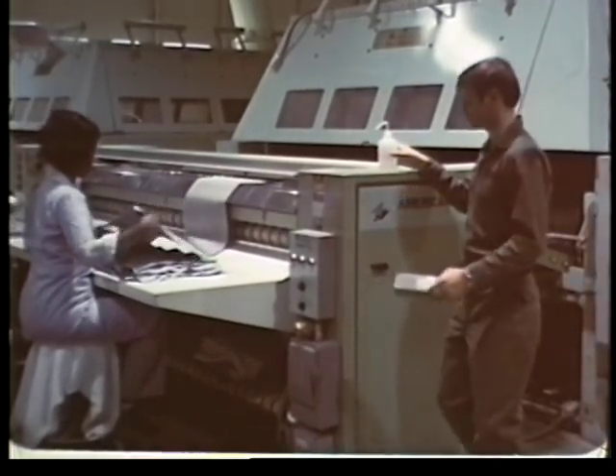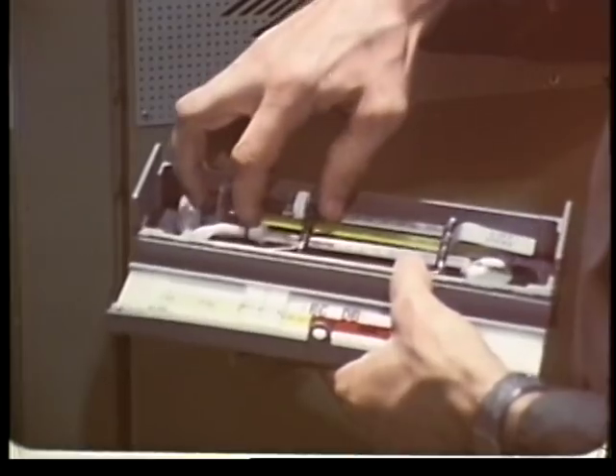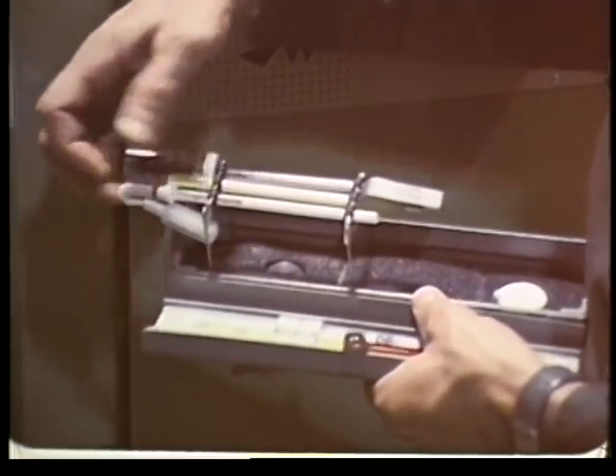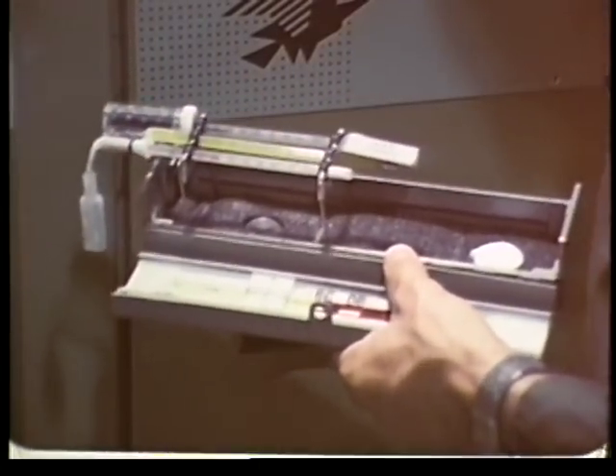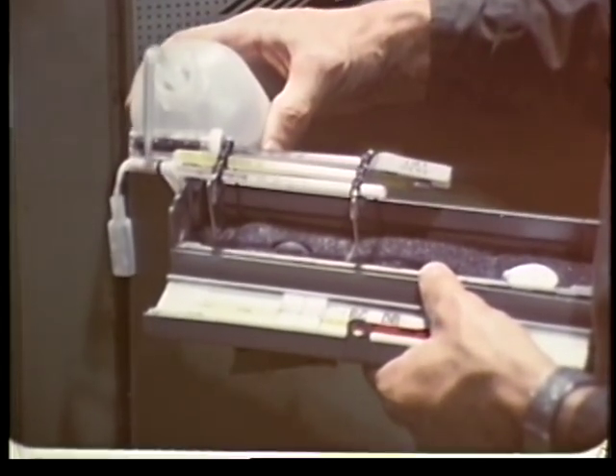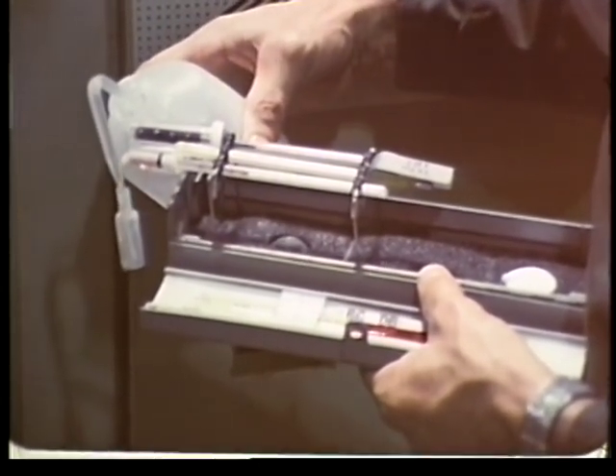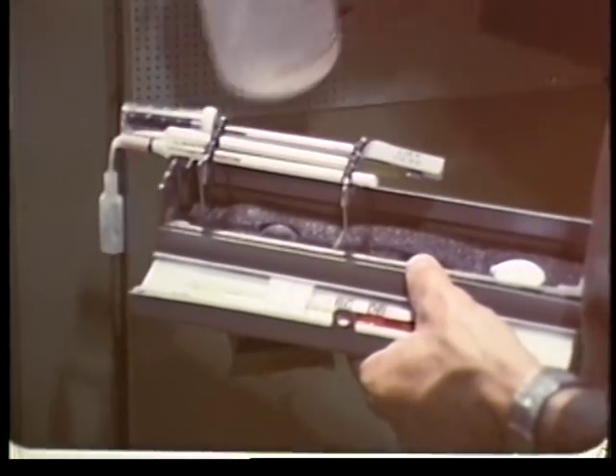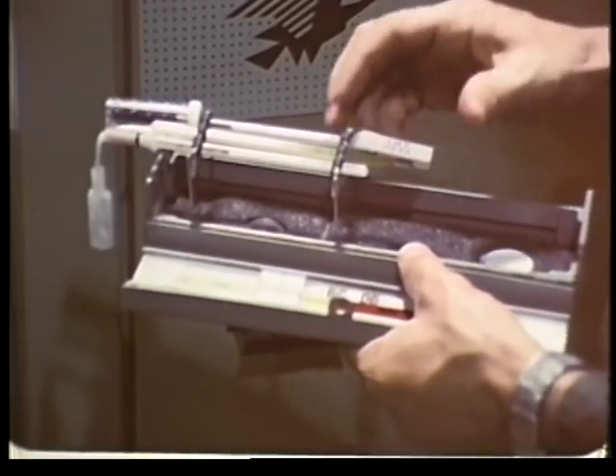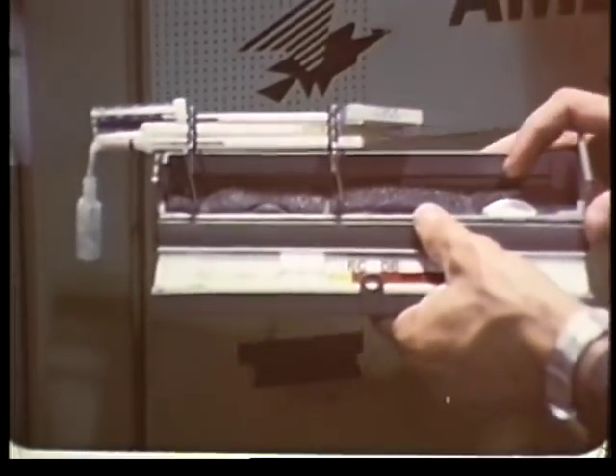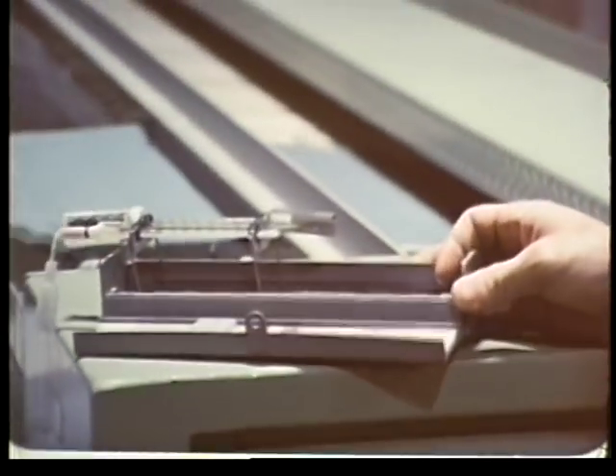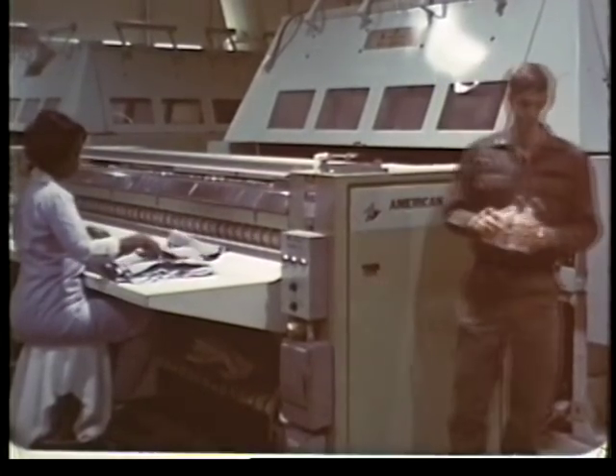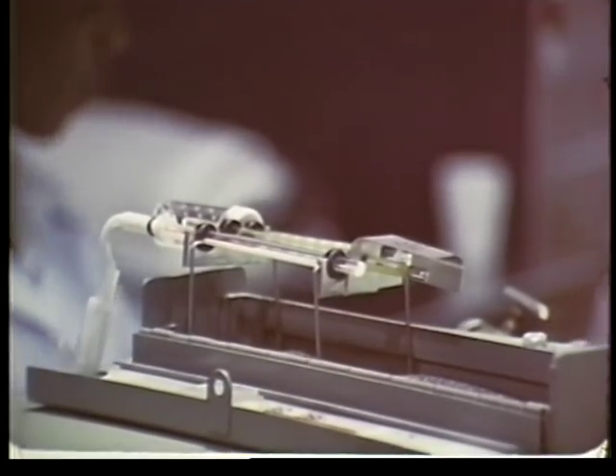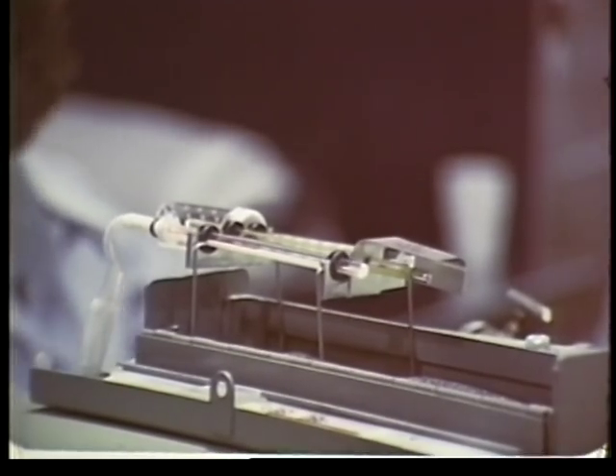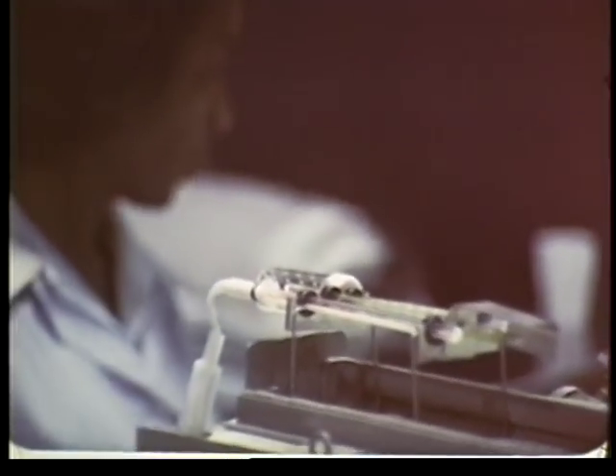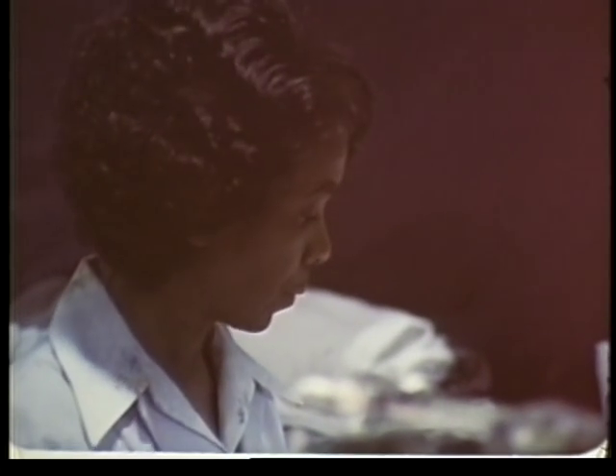You begin the evaluation phase of the survey at the inspection site. Temperature monitoring sites are selected from among areas suspected of producing heat stress problems. You then prepare the wet bulb globe thermometer kit by wetting the entire wick with distilled water and filling the reservoir. Set up the instrument and allow time for the readings to stabilize. Allow about a half hour for the first reading and 5 to 10 minutes for the ones after that. You're trying to determine the heat stress on the workers, so take your readings near where the workers are.